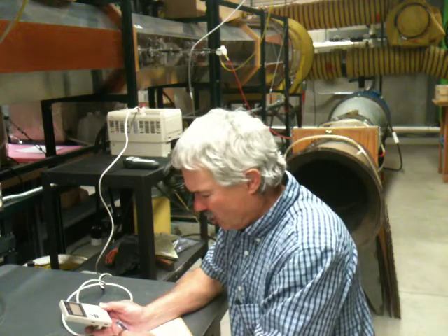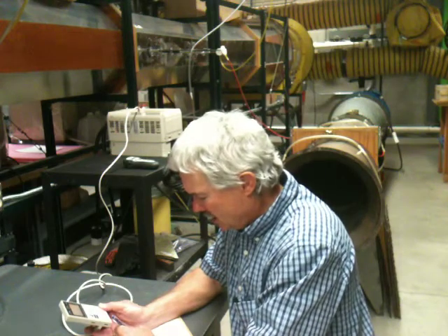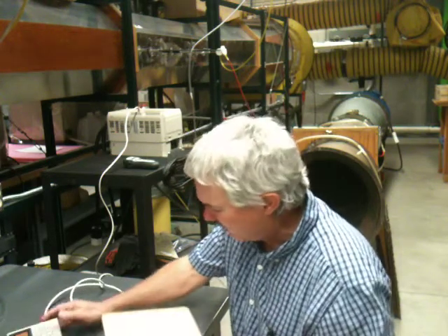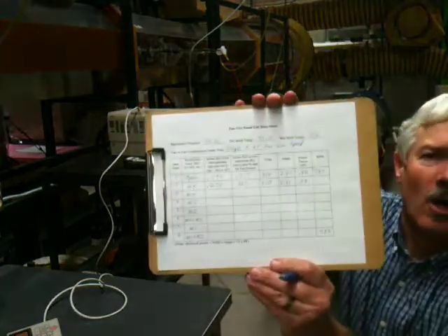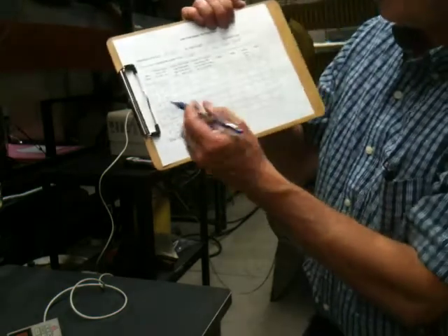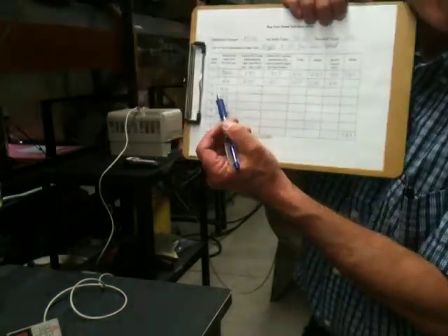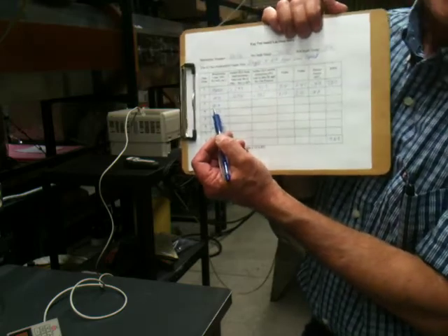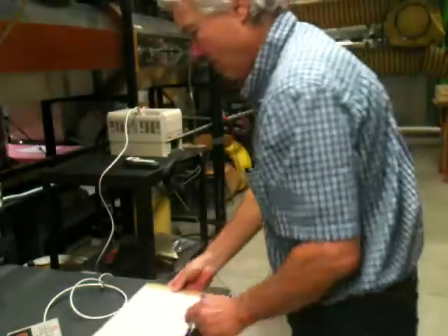Amperage is still 2.41. And power factor is still 0.40, okay? So that's our second data point. Again, goes pretty quickly. For the third data point, we'll remove the M5 restriction and put the M4 restriction in.